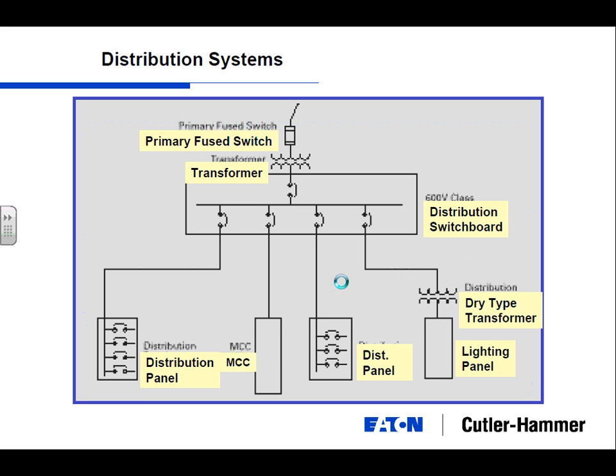But once you step into your distribution switchboard, that's the main board for the plant. That is the hub everything's coming out of, going down to your distribution panels, your motor control centers, smaller dry type transformers that may step this from 480/277 down to 120/208. This is the gist of the power distribution system that we look at in commercial facilities.